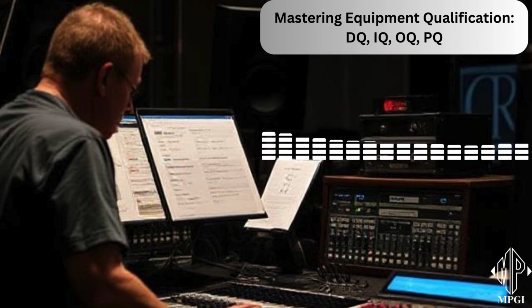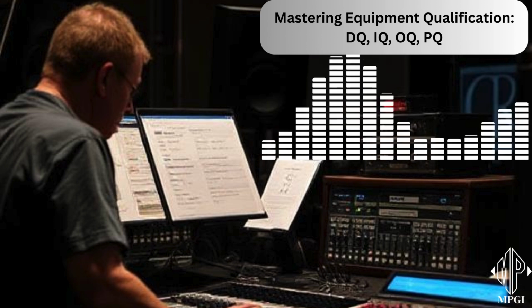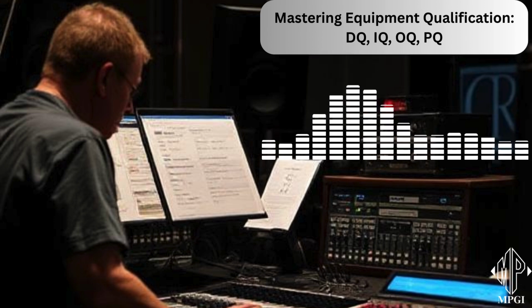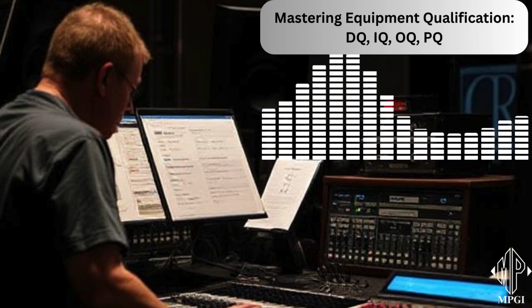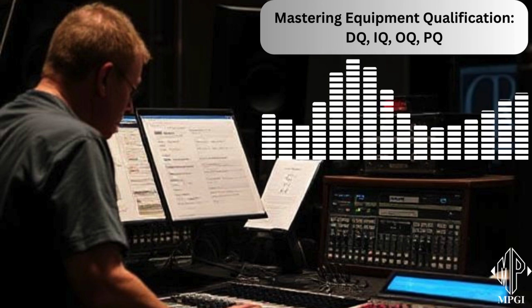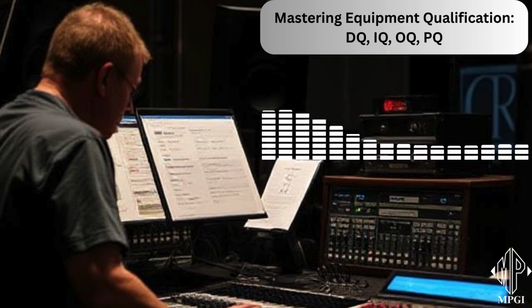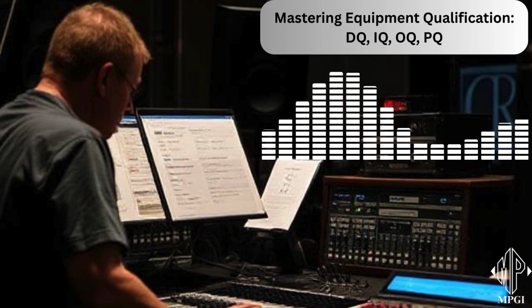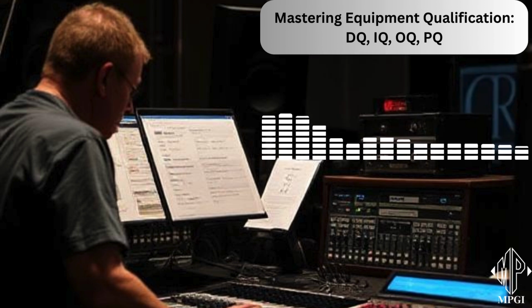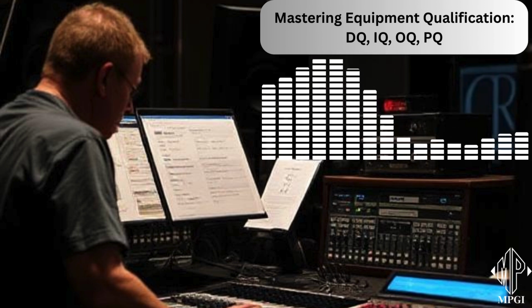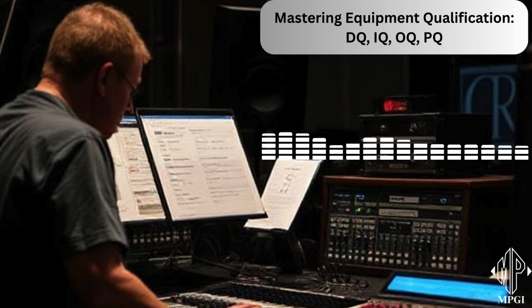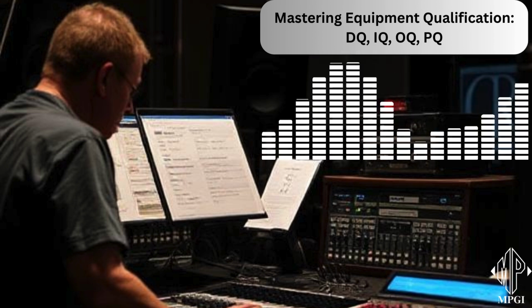Hmm. For a medical device, PQ might involve simulated use testing to ensure it performs as expected under real-world stresses. So basically putting it through the same wear and tear it would experience in a hospital or a patient's home. Exactly. And they might also evaluate the consistency of a packaging process over multiple runs. So making sure everything is packaged correctly and consistently every single time. So PQ is really about mimicking real-world use as closely as possible.